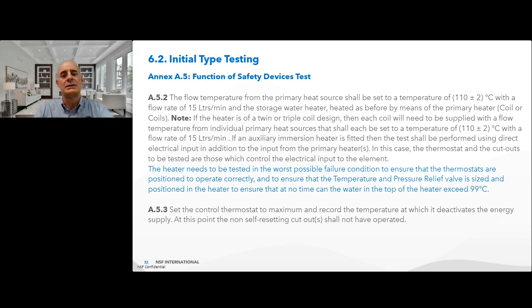If an auxiliary immersion heater is fitted, then the test should be performed using direct electrical input in addition to the input from the primary heaters or coils. In this case, the thermostat and the cutouts to be tested are those which control the electrical input to the element. The heater needs to be tested in the worst possible failure conditions to ensure that the thermostats are positioned to operate correctly and to ensure that the temperature and pressure relief valve is sized and positioned in the heater to ensure that at no time the water in the top of that heater exceeds 99 degrees.